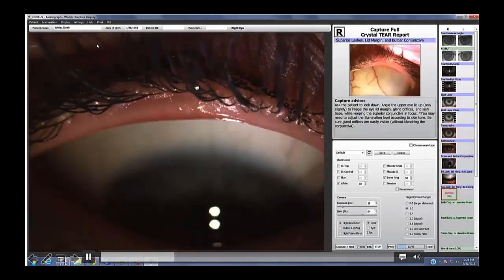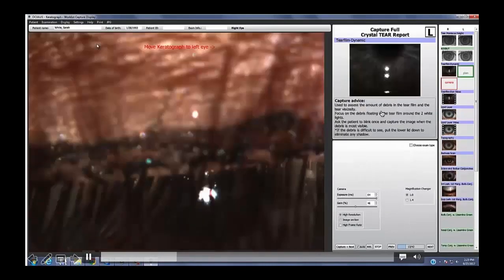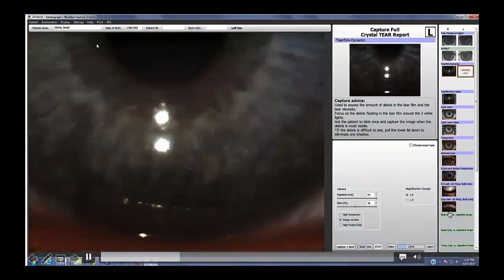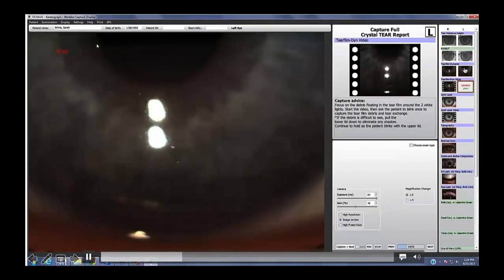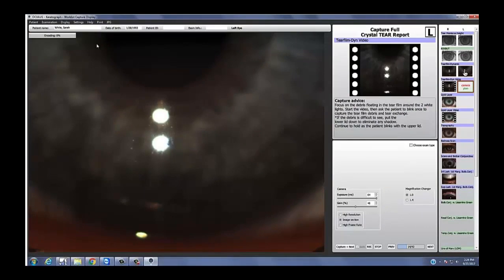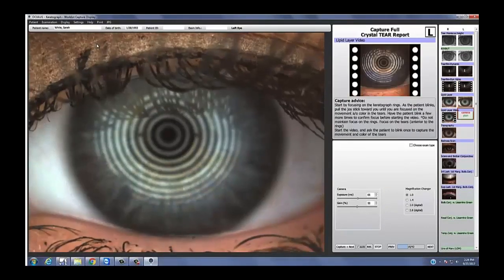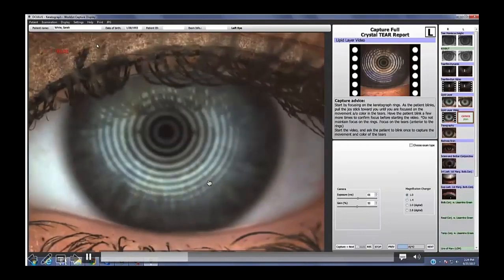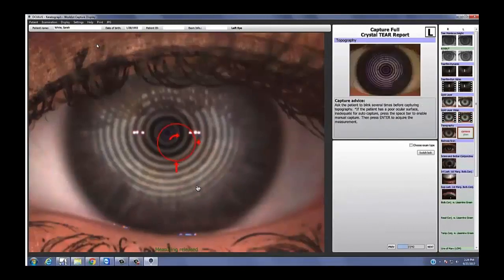We do the same thing on the top lid, focusing not just on the lid margin with the glands but also the lashes. The system tells the technician exactly what to do to get the results you're looking for. Once we've gone all the way through this sequence, this is the spot where we put dye in. We go back and start with the left eye, doing the same thing — but because it's streamlined, it saved a lot of time versus going right eye, left eye, right eye, left eye. There are a lot of things in here that were well thought out to save seconds.